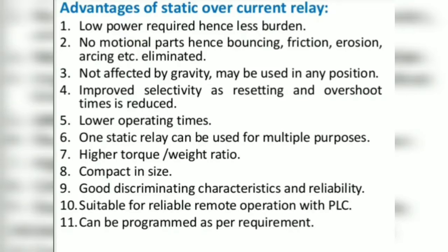If there is a moving part, gravity affects the moving part. If opposed to gravity, then the force required is very high. But in this static overcurrent relay there is no moving part, so it will not be affected by gravity, so we can use it in any position.